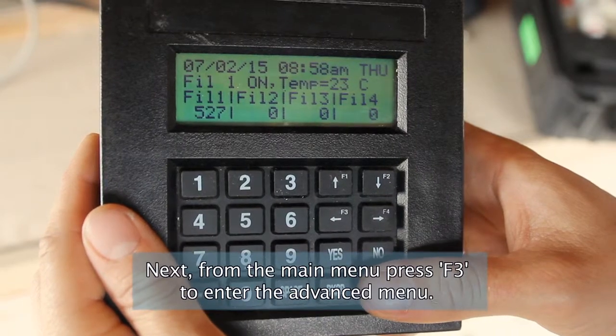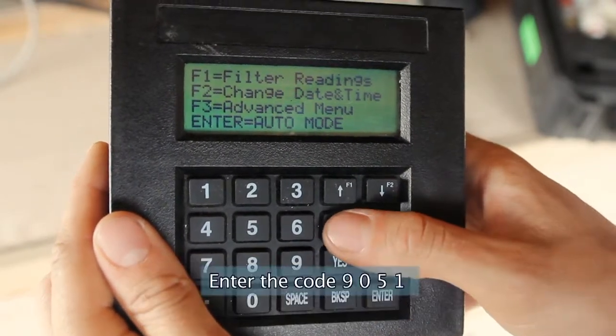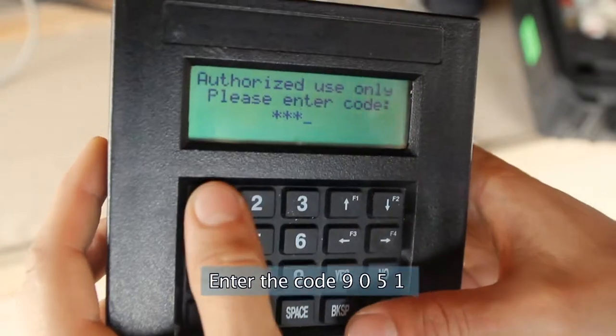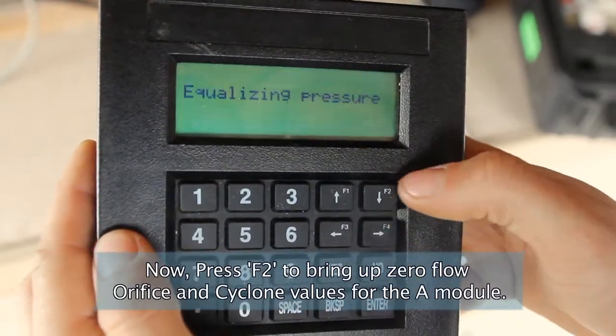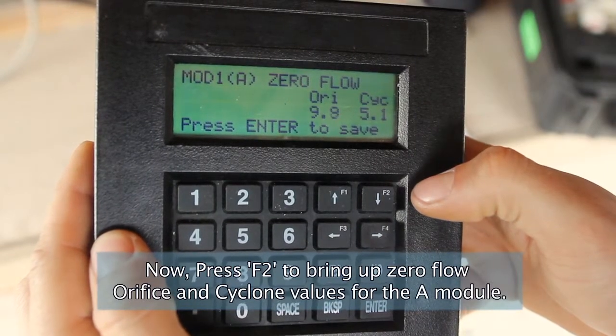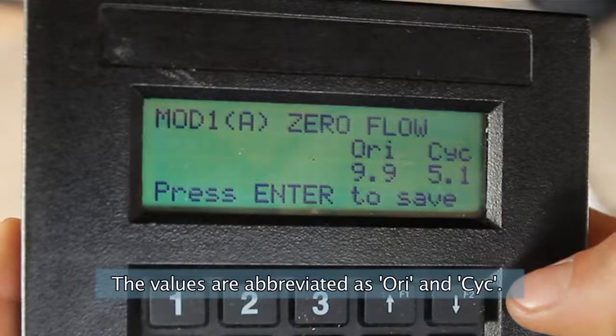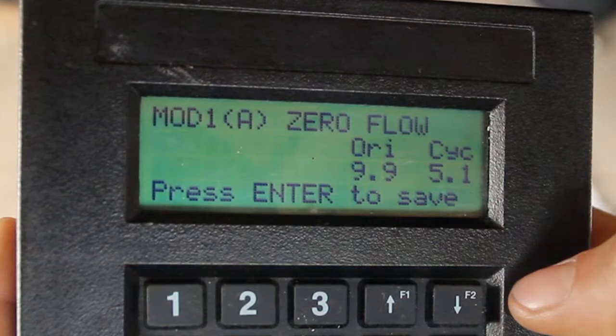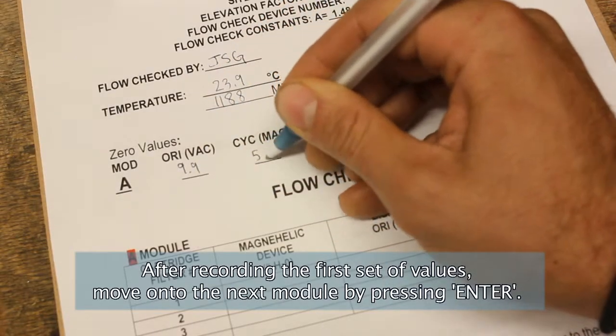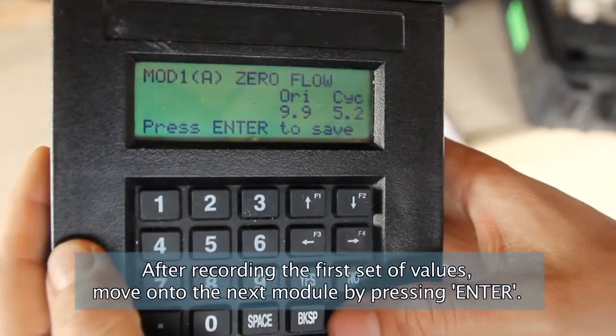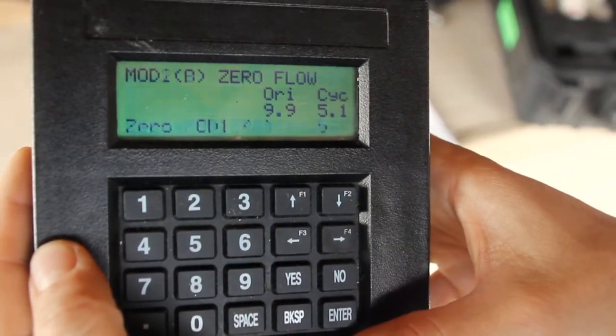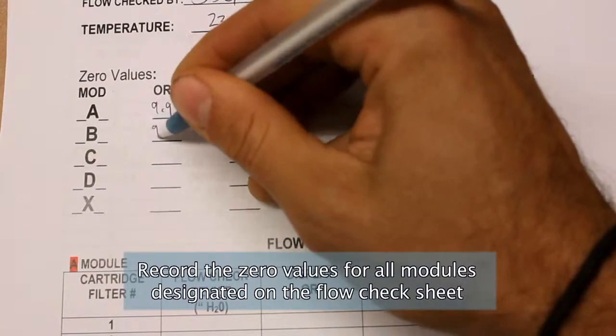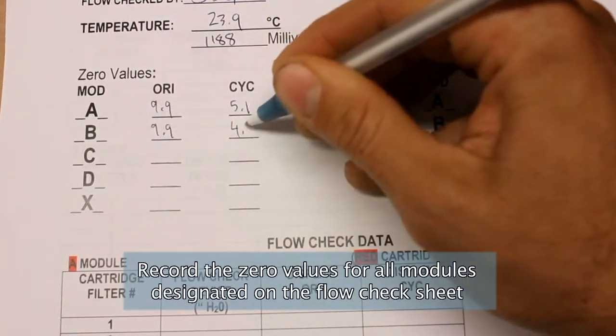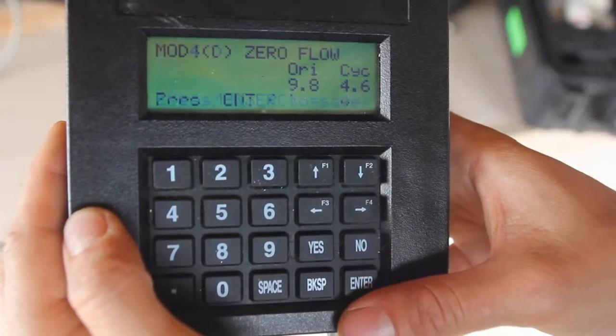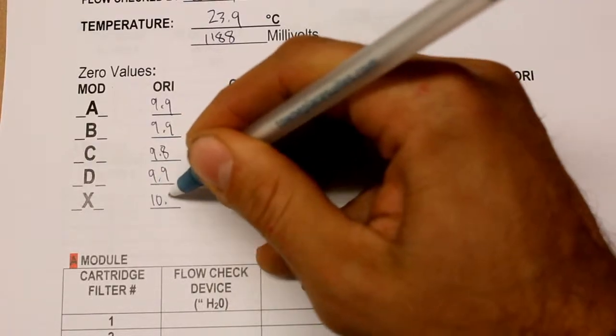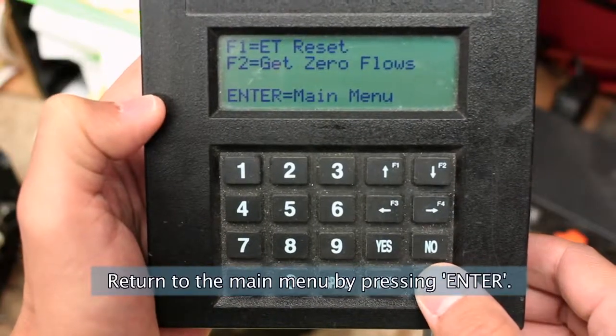Next, from the main menu, press F3 to enter the advanced menu, and enter the code 9051. Now press F2 to bring up zero flow orifice and cyclone values for the A module. The values are abbreviated as ORI and CYC. After recording the first set of values, move on to the next module by pressing Enter. Record the zero values for all modules designated on the flow check sheet. Return to the main menu by pressing Enter.